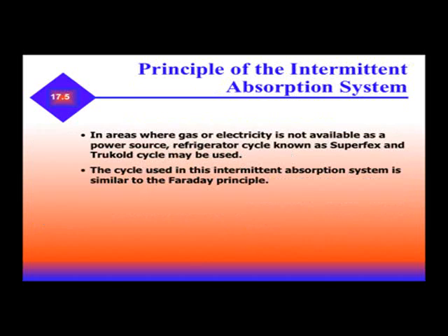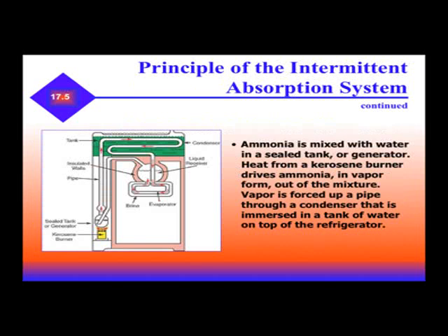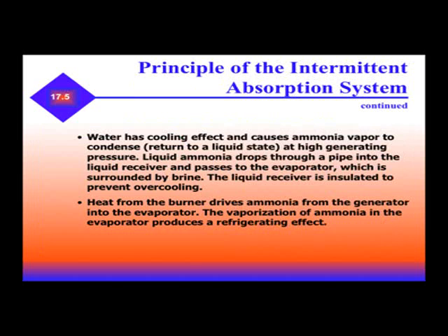The intermittent absorption system is used in areas where gas or electricity is not available. A power source or refrigeration cycle known as Superfex and Trukold may be used. This cycle, used in intermittent absorption systems, is similar to the Faraday principle. Ammonia is mixed with water in a sealed tank or generator. Heat from a kerosene burner drives ammonia in vapor form out of the mixture. Vapor is forced up the pipe through a condenser immersed in a tank of water on top of the refrigerator. At high generating pressure, liquid ammonia drops through the pipe into the receiver and passes to the evaporator, which is surrounded by brine.